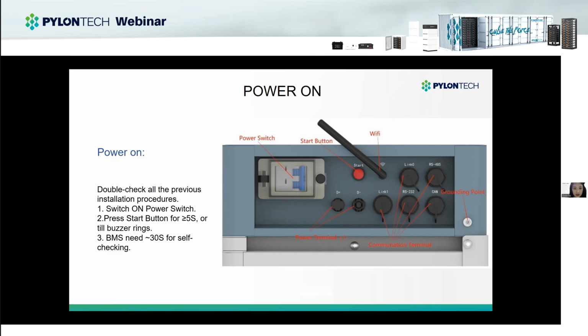When you see the red light on the front side of the BMS, it shows the connection is successful. And when there is a breaker between the BMS and inverter, and the breaker is tripped off because of overcurrent or short circuit, you have to wait for more than 10 minutes and then turn it on again. Otherwise, it could cause breaker damage.